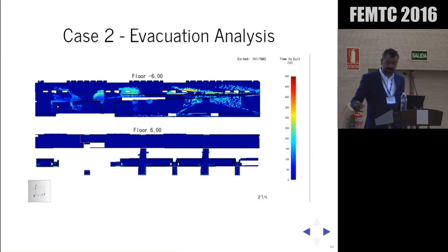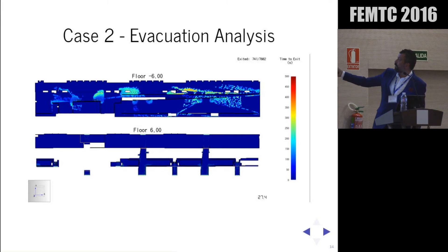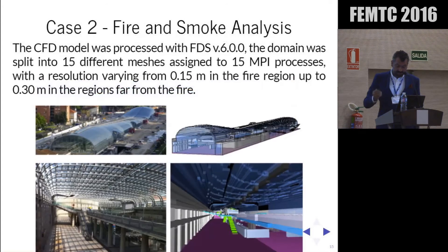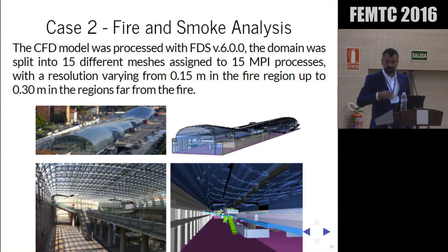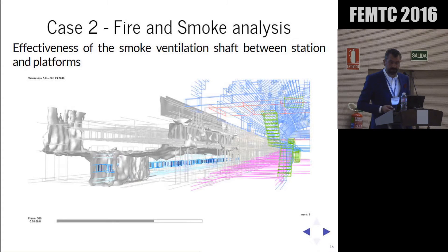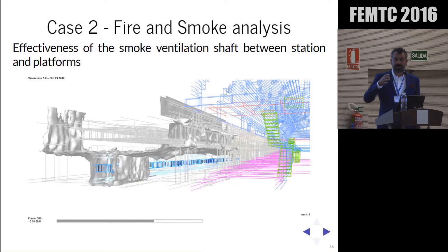For the evacuation analysis, we looked at the current configuration and optimized all exits — there were issues with a big ramp and people being redirected from the back of the station. We then compared this with fire smoke modeling. For this large station volume, the FDS model used 15 different meshes ranging from 0.15 to 0.3 meters. The results showed people could achieve safe conditions, and crucially, there were shafts between the station and the tunnel — most of the smoke escaped through these natural shafts.